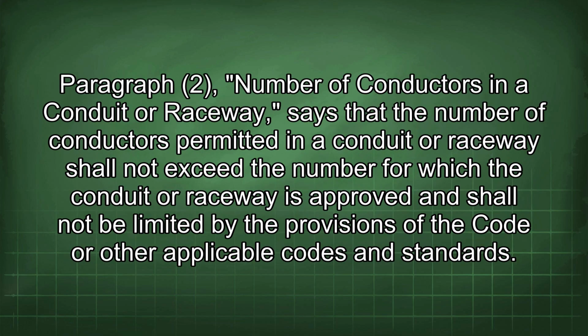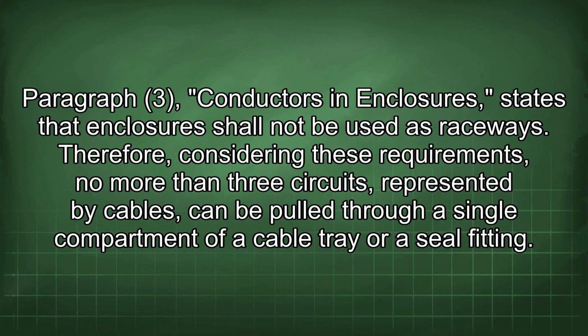Paragraph 2, Number of conductors in a conduit or raceway, says that the number of conductors permitted in a conduit or raceway shall not exceed the number for which the conduit or raceway is approved and shall not be limited by the provisions of the code or other applicable codes and standards. Paragraph 3, Conductors in enclosures, states that enclosures shall not be used as raceways.